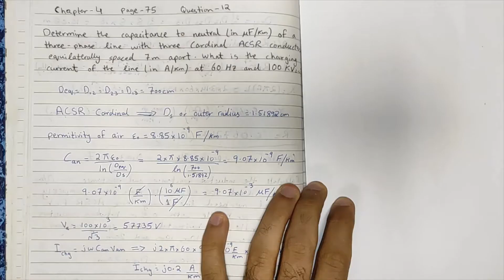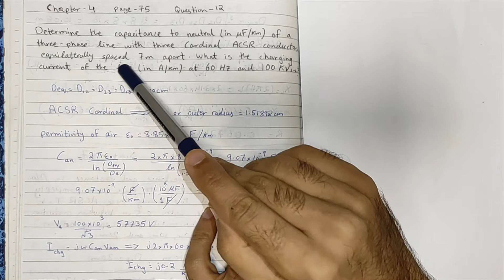This is question number 12 from chapter number 4, which can be found on page number 75 of the book. The question says: determine the capacitance to neutral in microfarads per kilometer of the three-phase line with three Cardinal ACSR conductors equilaterally spaced 7 meters apart. What is the charging current of the line in amperes per kilometer at 60 Hz and 100 kV line to line?